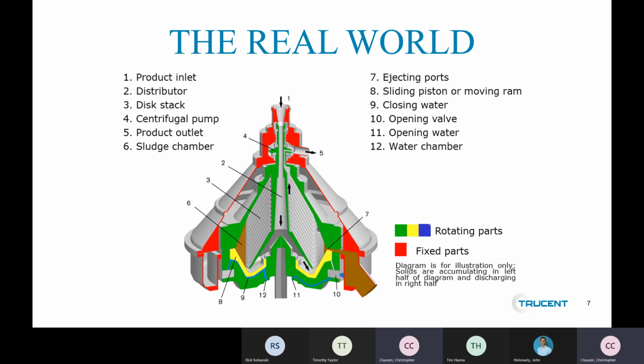If you look at the brown section on the left, labeled 6, that's where those solids start to build up on the side of the bowl. Depending on the size and design of each centrifuge out there, that solids capacity is different, and when we get into selecting a centrifuge, we'll talk about that more.